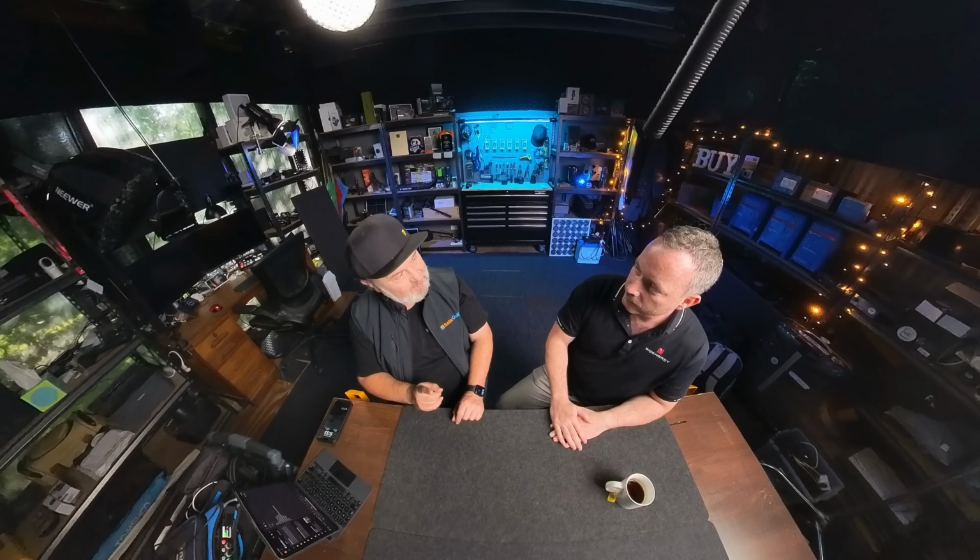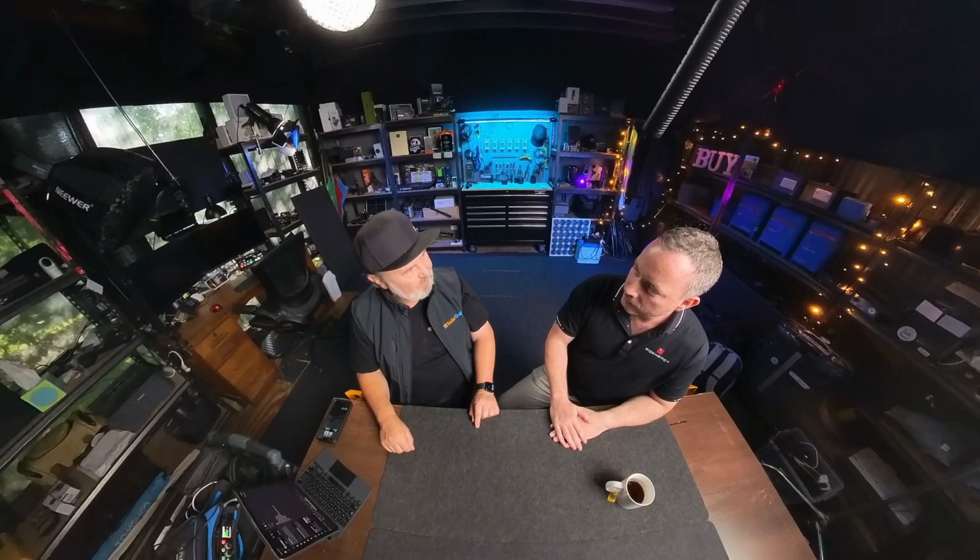Now, just going back to that first statement you made, we paralleled 7 of them together. Yes. What I also found interesting is that for off-grid, I'm used to having inverters with 2 AC ports, like an input port, typically a generator, and a load port, typically the loads in the home. Yep. But with the SigenStor, it's got 1 AC port, effectively a T connection to both the generator and the load through this magic box called the gateway.